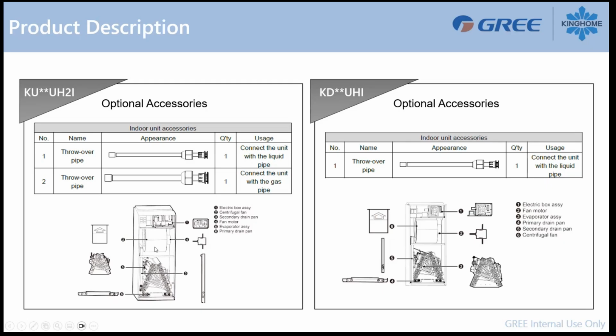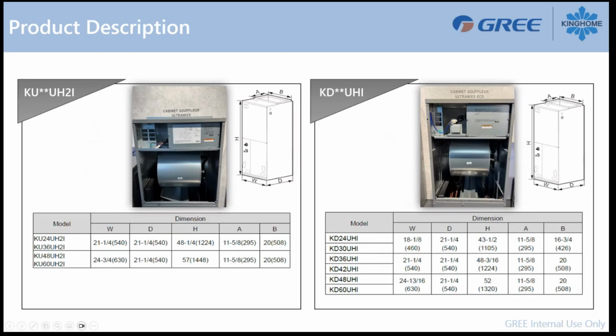You have your blower wheel and your blower motor. On top of the evaporator coil, both systems have two different drain pans, and you have the electrical board on the top of the air handler. If we take a quick look at the dimensions, the KU uses two different cabinets. We have a 2-ton and a 3-ton using the same dimension, and a 4-ton and a 5-ton using the same dimension. So 24 by 21 by 57 for the height for the 4 and 5-ton.